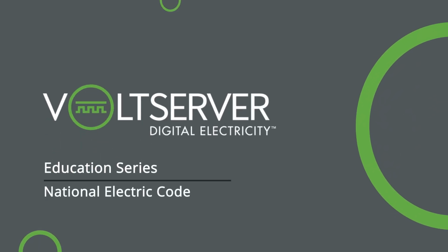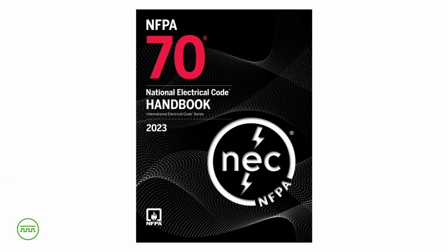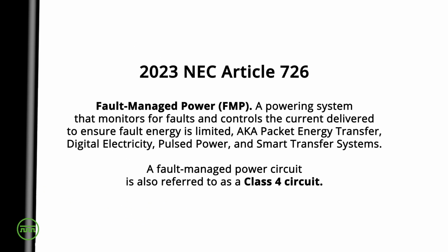The 2023 version of the National Electric Code adopts UL 1400 and introduces fault-managed power for the first time. It's unique and specialized enough that it calls for its own code section. The new Class 4 classification standard was created especially for fault-managed power systems.